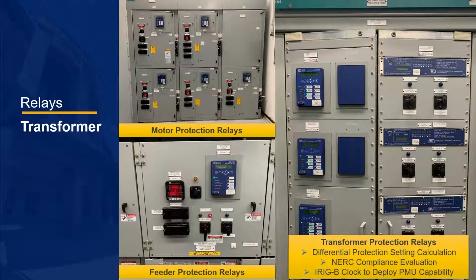The last of the relays replaced were the generator step-up, GSU, and balance of plant unit aux transformer protection relays. Transformer relays are generally a more complicated relay with multiple functions encompassed in the protection scheme. Differential protection settings were calculated taking into consideration other systems, in this case, the generator static frequency starting system. Also, a NERC compliance evaluation was detailed as required in the PRC standard. Another feature added was the IRIG-B GPS clock to support the deployment of the Phasor Measurement Unit, or PMU, capability within the relay.